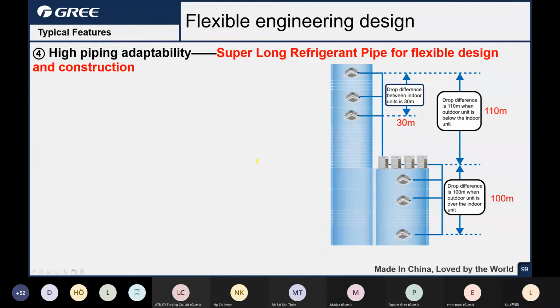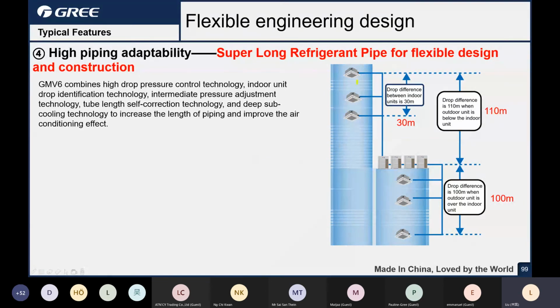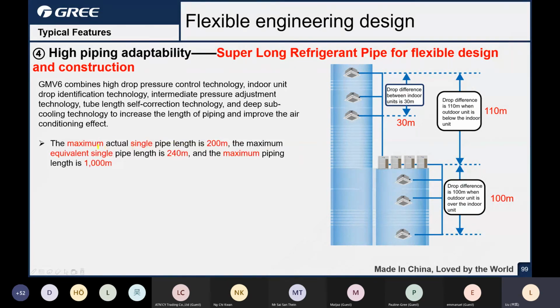Next one is the pipelines. For the indoor units, the height difference is 30 meters. And for the indoor units and the outdoor units, the height difference is 110, depending on the location of the outdoor units. If indoor units are upside, 110. If outdoor units are upside, that's 100. And for the other, the maximum single pipe is 200 meters, and the maximum equivalent single pipe is 240 meters.